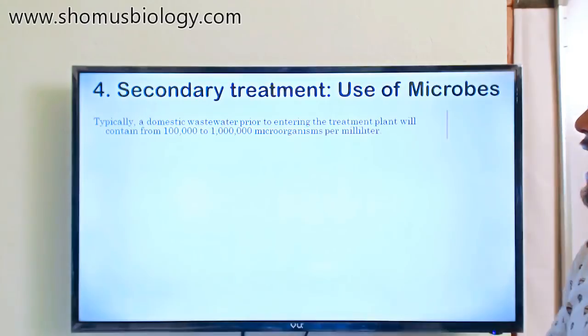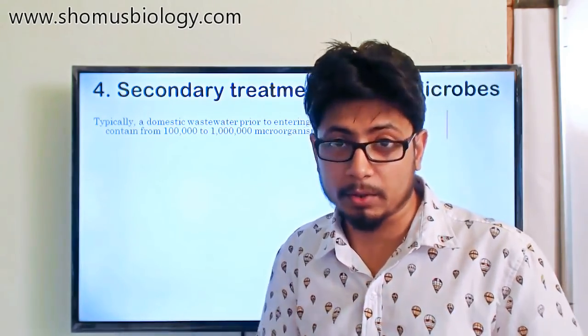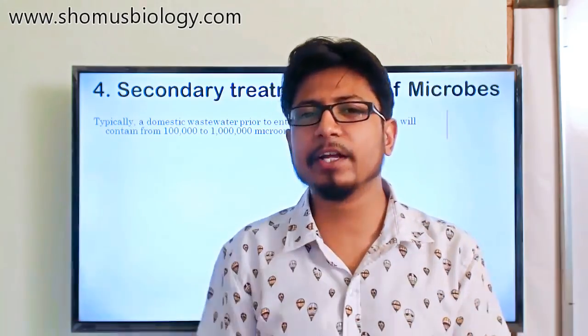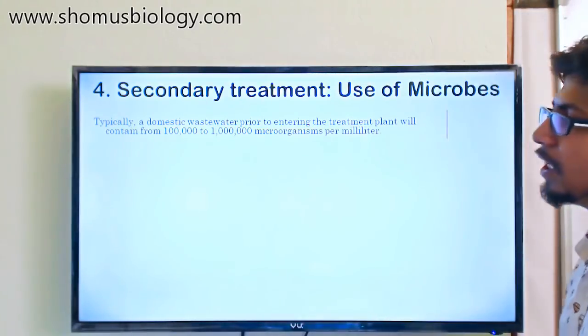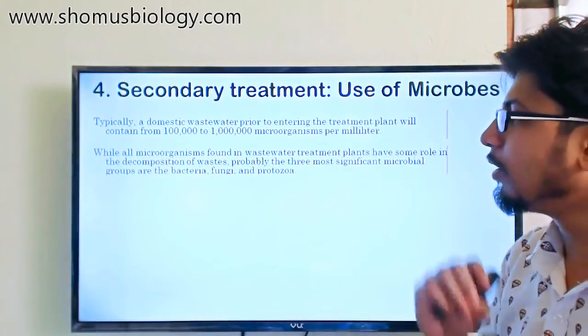Regarding the microorganisms used in secondary wastewater treatment: a typical domestic wastewater entering the treatment plant contains one lakh to ten lakh microorganisms per milliliter. Those microorganisms can do their job, but we still need to add additional microorganisms from outside. We take a sample, analyze what kind of organic matter and solids are present, and then introduce an appropriate array of microorganisms accordingly.